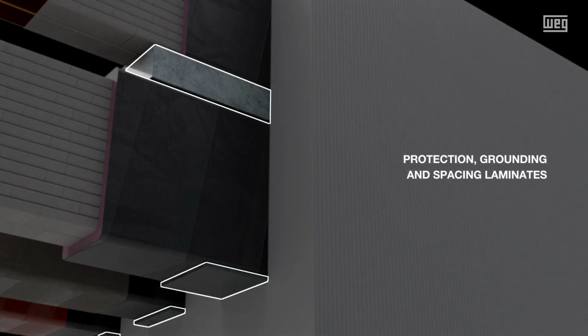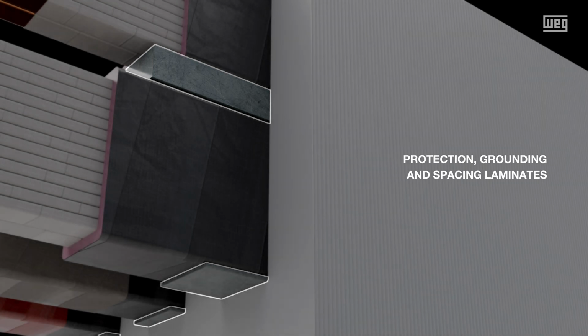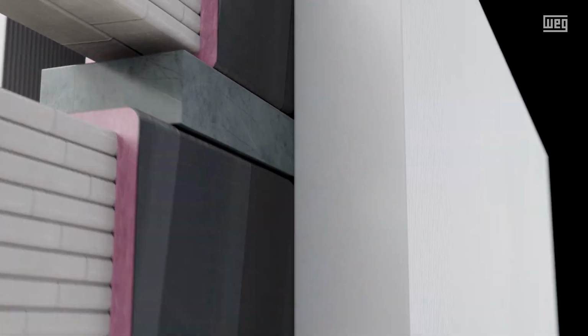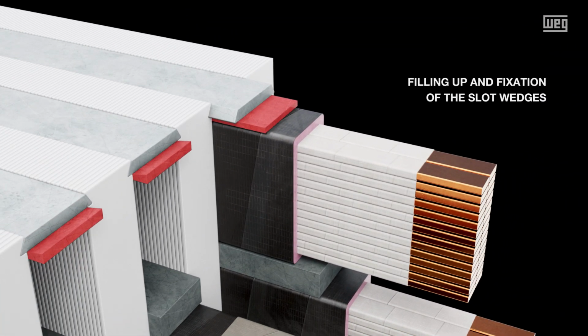Rigid laminates are placed at the bottom of the slots and between the upper and lower layers of the winding. These laminates, in addition to the mechanical protection of the insulation during the production, ensure proper spacing between coils and contribute to an improved grounding of the groundwall insulation surface along the slots.